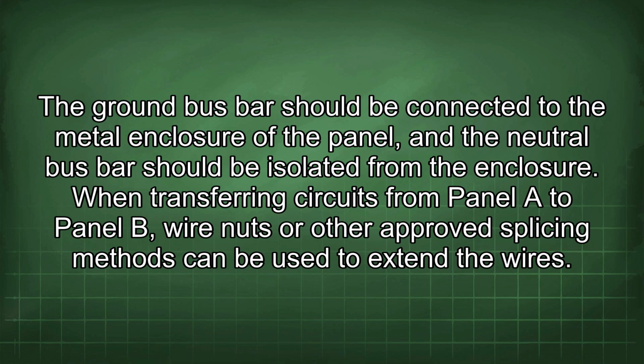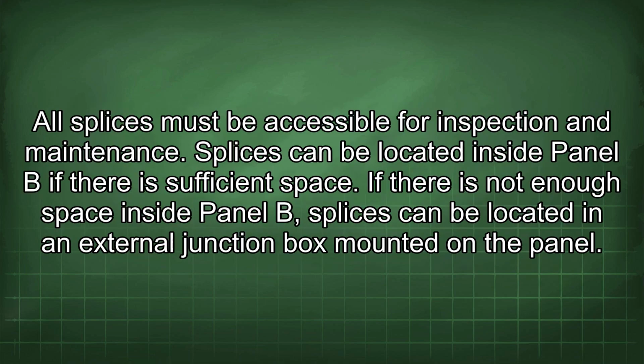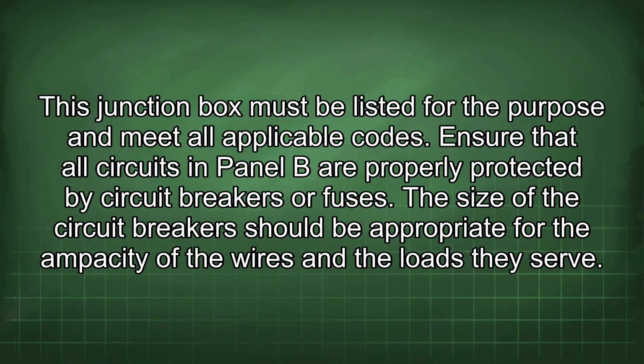When transferring circuits from panel A to panel B, wire nuts or other approved splicing methods can be used to extend the wires. All splices must be accessible for inspection and maintenance. Splices can be located inside panel B if there is sufficient space. If there is not enough space inside panel B, splices can be located in an external junction box mounted on the panel. This junction box must be listed for the purpose and meet all applicable codes.